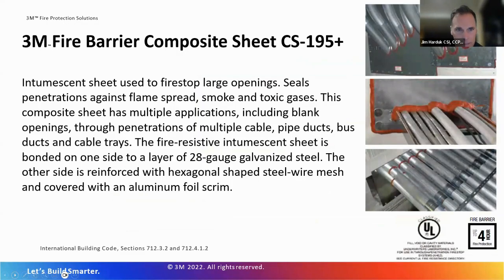Composite sheet. Composite sheet, what that is, it's an intumescent material that has a galvanized steel plate on one side and a foil scrim on the other. Again, this is a cost-effective way to close down large openings in fire-rated floor and wall assemblies. Typically, we use these a lot of times where we have multiple conduit or if we have cable trays. And the best way to install this is you have your rough opening, you attach this to your surface if it's the floor or wall, and then you go back with your core saw, and you cut your openings and pull whatever the penetrating item is through that. Next slide.